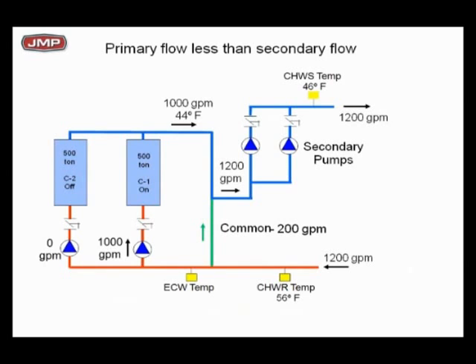But here's what gets to be interesting. I'm bringing 1200 GPM back at 56. But where is the 200 GPM coming from going south to north to mix with 1000 GPM of 44? It has to be 200 GPM of 56 degree water. So I've got 1200 GPM going to the bottom T at 56. I got 1000 GPM at 56 going over to my first chiller. That leaves 200 GPM going north of hot 56 degree water mixing with 1000 at 44 to give me 1200 GPM at 46 degree water.